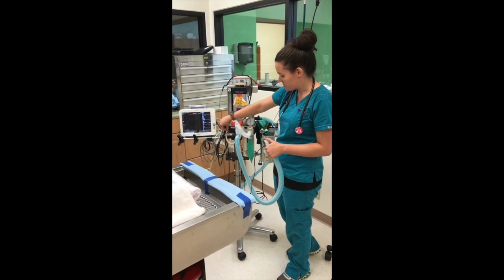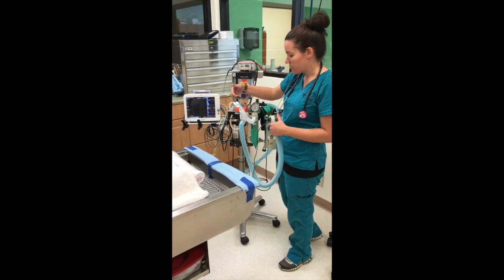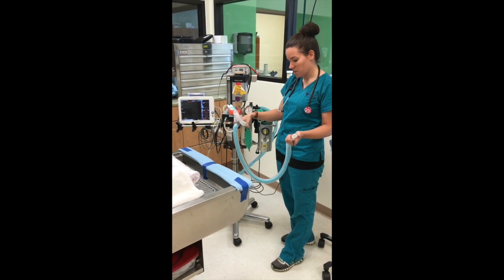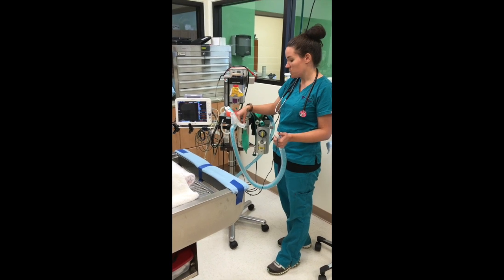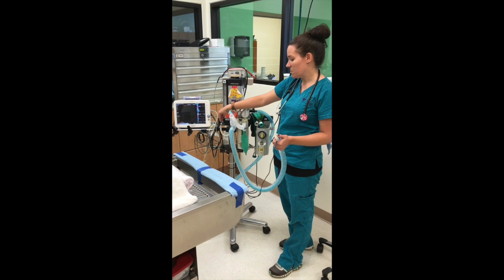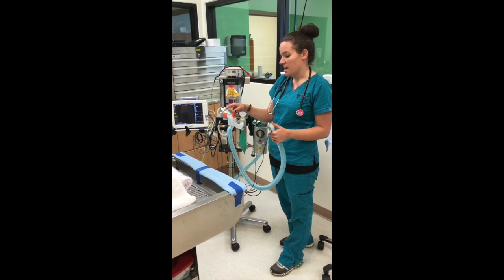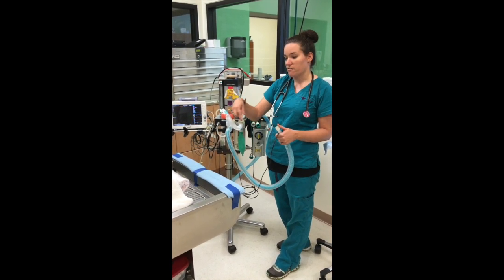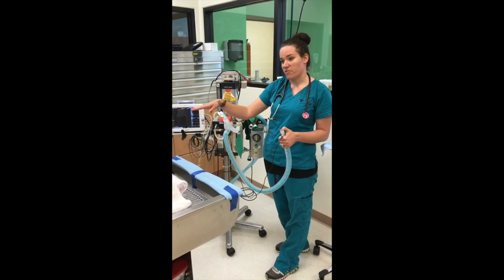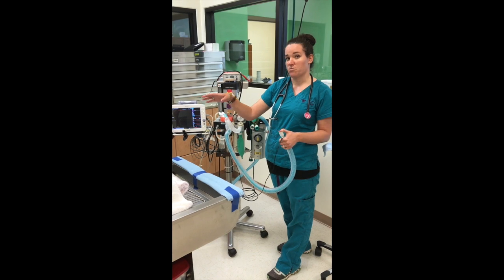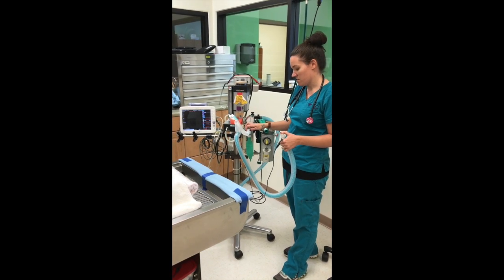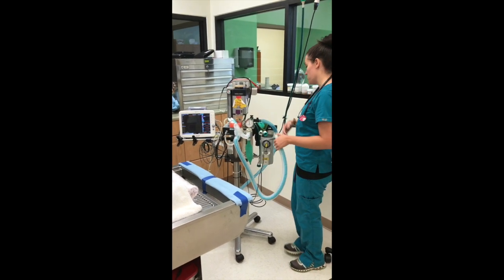This is the fresh gas outlet here. If we were using a non-rebreathing system, we would take this tubing off, hook the new tubing in here, and then our fresh gas tube would go here. In that system, they breathe in the fresh air. The exhaled air goes straight into the F-air canister to be filtered into room air. They don't rebreathe that at all. With this system, they're rebreathing some of the gas that's coming through the system.